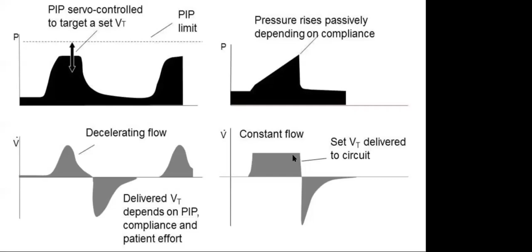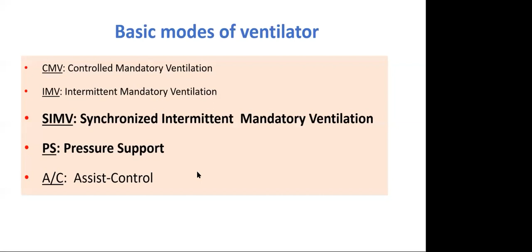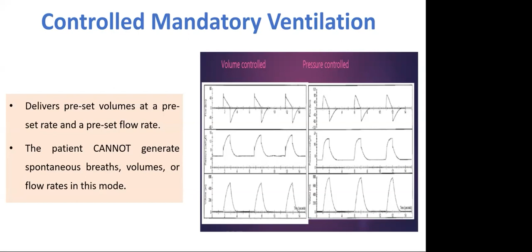So what are the basic modes of ventilator? I'm not going to go into detail. I will just tell about the basic principles. So controlled mandatory ventilation, synchronized intermittent mandatory ventilation, which is commonly used, and assist control. Okay, what is controlled mandatory ventilation? The name itself says it: it delivers whatever you set. In between, whether the patient breathes or not, it won't bother. If you set 20 breaths, it will deliver 20 breaths. The patient cannot generate any spontaneous breaths, volumes, or flow rates in this mode.